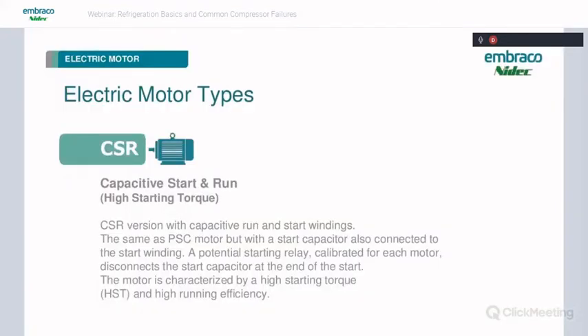And then we have a CSR, which is capacitive start and run. So we have high starting torque and high running torque. So we've got the high starting torque for hard starting applications and high running torque to give it better efficiency. You're going to see this in a lot of your larger commercial compressors, especially 1 horsepower and above, 115 volt. You have extremely high locked rotor amps in a compressor like that. So they're going to use that start cap to help alleviate that extremely high starting current. And then an addition of a run capacitor to give it a little bit better running efficiency with these larger compressors. So currently Embraco goes up to 2 horsepower, but I believe in 115 volt, it's only 1.5 horsepower. So you're always going to see a CSR motor in that type of application.